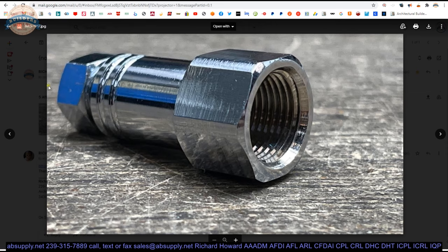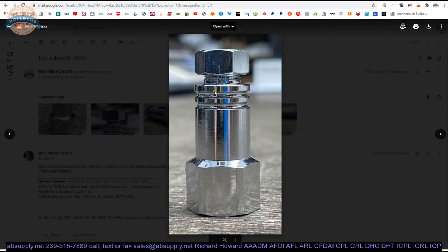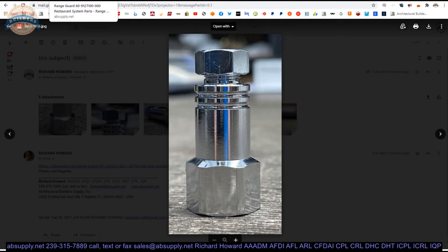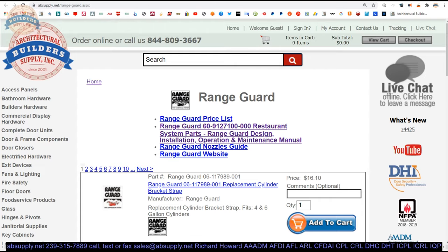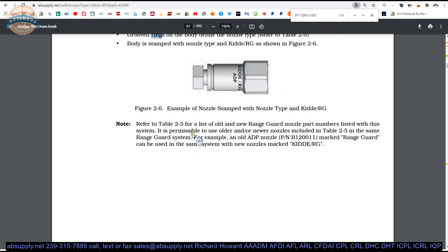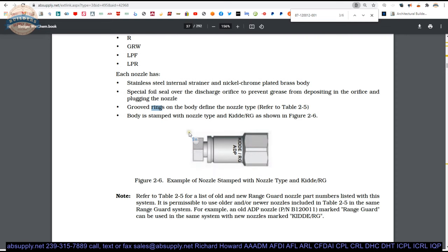Groove rings on the body define the nozzle type. So if you recall, there are grooved rings. That is basically the reason those are there is so that anyone, an inspector, an installer, an owner can look at the nozzle from a distance and understand visually what nozzle is installed there based on those rings.